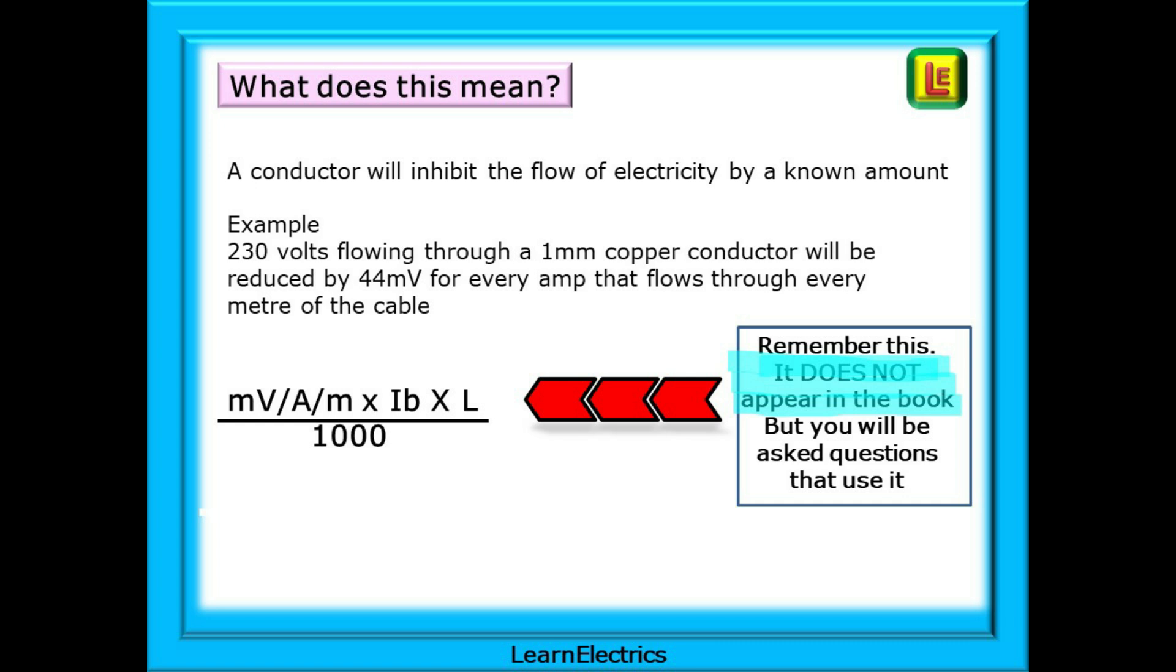230 volts flowing through a 1mm copper conductor will be reduced by 44 millivolts for every amp that flows through every meter of the cable. Here is the formula to use. The millivolts per amp per meter is obtained from the tables section of the book. IB is the design current. It is the maximum current that is expected in the circuit and the length is in meters. We divide all that by the number 1000 to convert millivolts into volts so that we can compare the answer directly with the 3% or 5% maximum permitted values. You must remember this formula. It does not appear in the wiring regulations book which is the only book allowed in the exam. But you will be asked questions on voltage drop and you will be expected to use this formula.